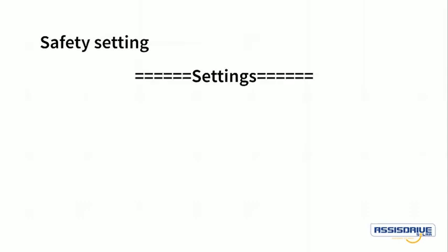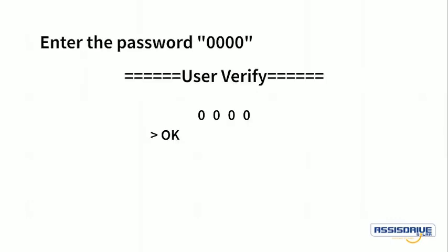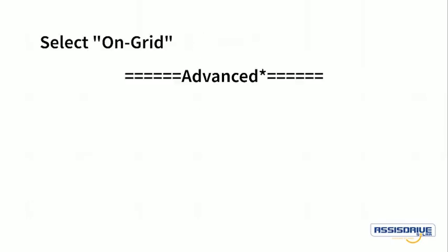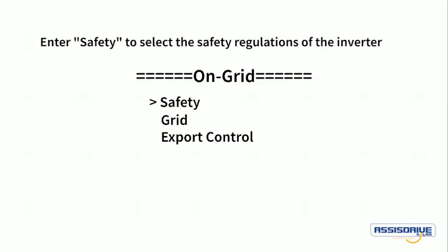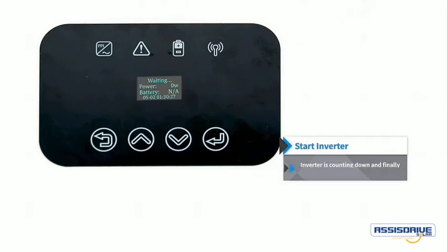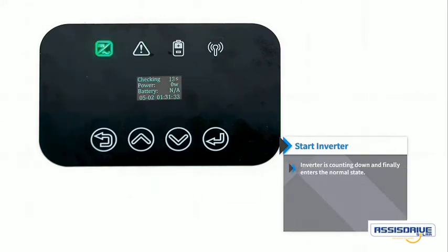Safety setting, enter the main menu, settings, select advanced. Enter the password 0000, select on grid. Enter safety to select the safety regulations of the inverter. Inverter is counting down and finally enters the normal state.